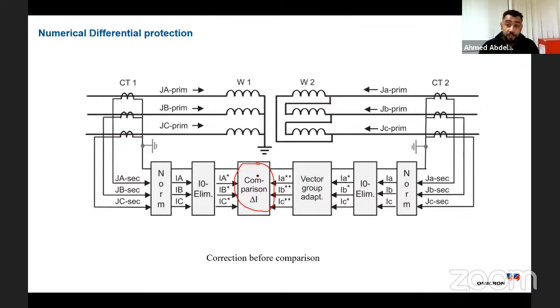I just need to define the transformer itself to the relay, the vector group, and define the polarity of the CT, and at the end the relay itself will calculate. This is what we can call the numerical differential protection. So the correction before comparison needs to be done not by a resistor and CTs, but by numerical means. So let us say, what are the corrections I need to define or do before comparing?